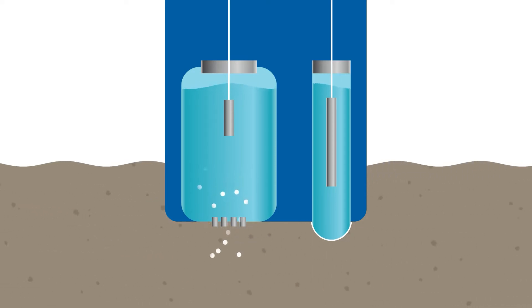When a pH sensor is used in dirty water, solids, oils, and sludge coat or plug the pores in the reference junction, blocking the flow of ions and disrupting the electrical connection between the electrodes. When this happens, the pH reading becomes unstable and the sensor must be cleaned or replaced.